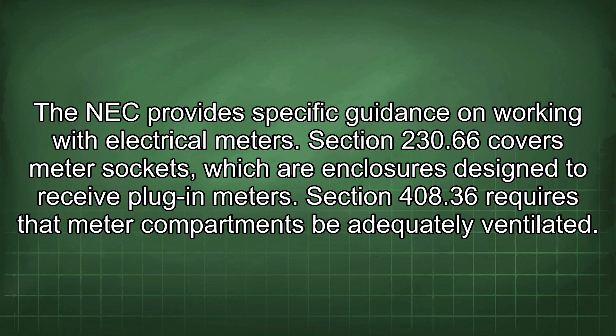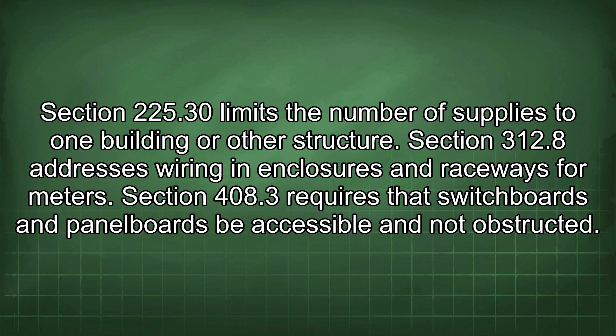Section 312.8 addresses wiring in enclosures and raceways for meters. Section 408.3 requires that switchboards and panel boards be accessible and not obstructed. Section 110.26 provides workspace requirements for electrical equipment. It is essential to follow these requirements to ensure the safety and accessibility of electrical meters.